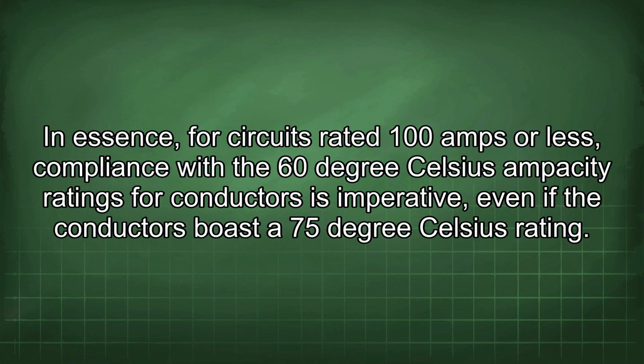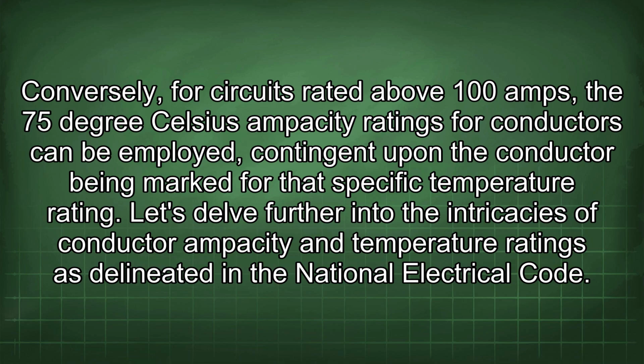In essence, for circuits rated 100 amps or less, compliance with the 60 degrees Celsius ampacity ratings for conductors is imperative, even if the conductors boast a 75 degrees Celsius rating. Conversely, for circuits rated above 100 amps, the 75 degrees Celsius ampacity ratings for conductors can be employed, contingent upon the conductor being marked with that specific temperature rating.